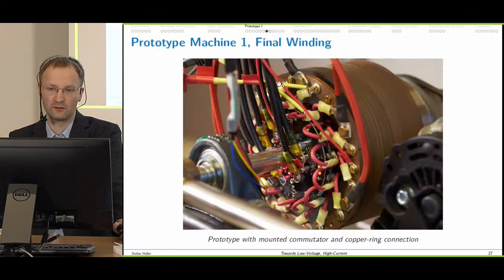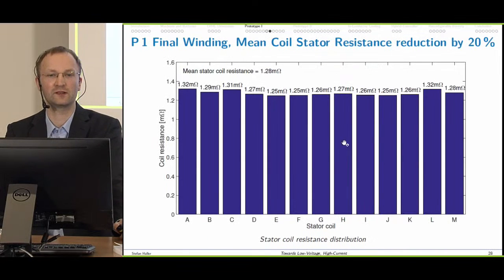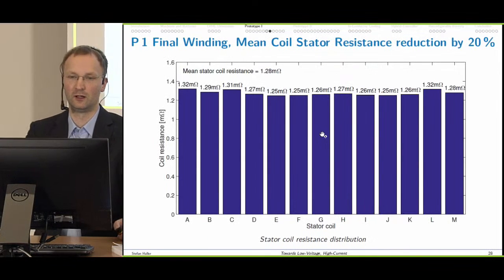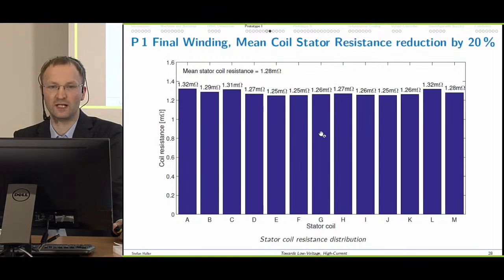So we changed the connection to a machined ring, shortened the stranded wire coils, and tried to get a low resistance connection. The result of that effort is that we now have a mean stator coil resistance of 1.28 milliohm and much less resistance spread.